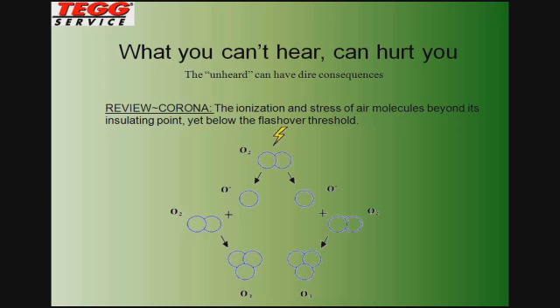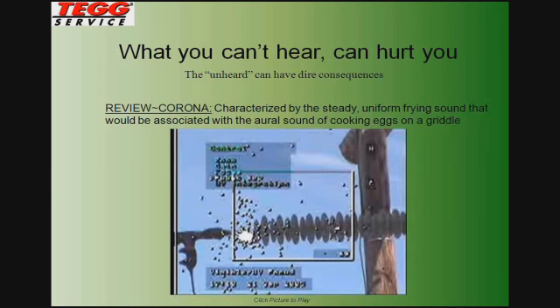There's a lot of what we call nuisance corona out there, meaning it's a naturally occurring thing. If anybody has listened to AM radio and they've driven under high-tension power lines and you hear the quote-unquote interference, that is nuisance corona. It's a natural thing because those higher voltages are stressing the air, the magnetic field is expanding and collapsing, and it agitates the air molecules.